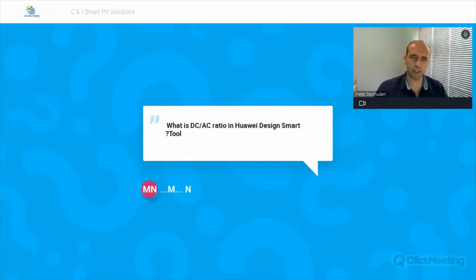What is the DC to AC ratio in Huawei Design Smart tool? DC to AC ratio, I think it's country specific. Huawei has got a certain table where they've done case scenarios in various countries with the specific irradiance that's applicable to the area. So I know it can vary a bit, but normally the DC to AC ratio is between 1.2 and 1.4, with about 1.3 being the sweet spot.